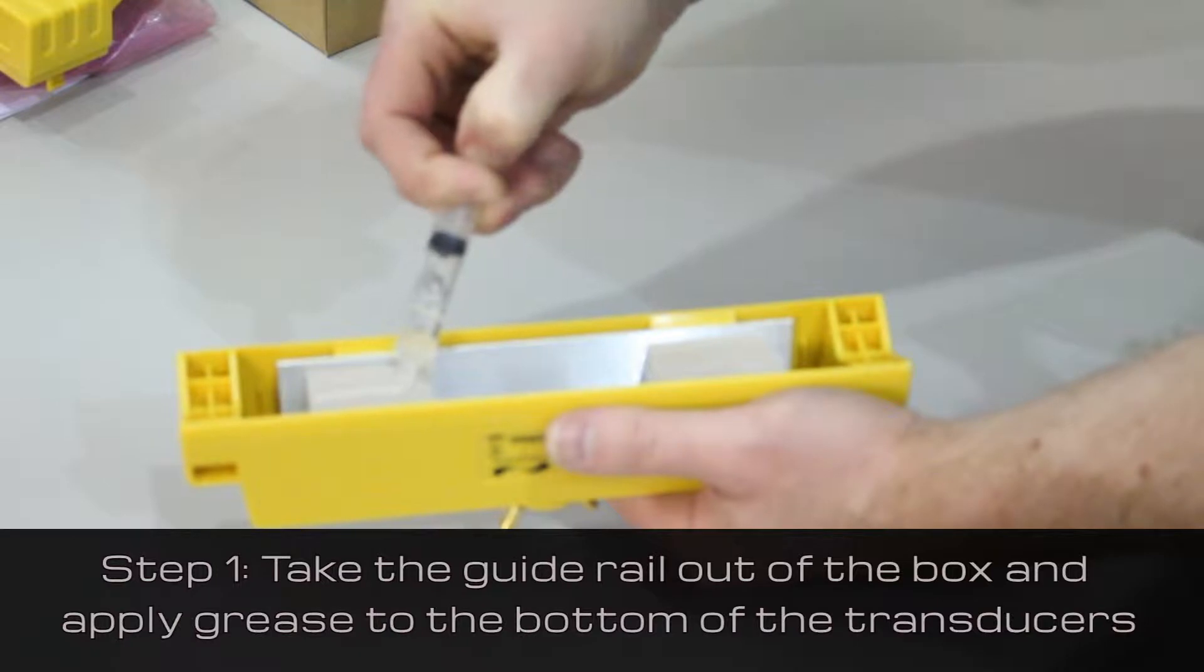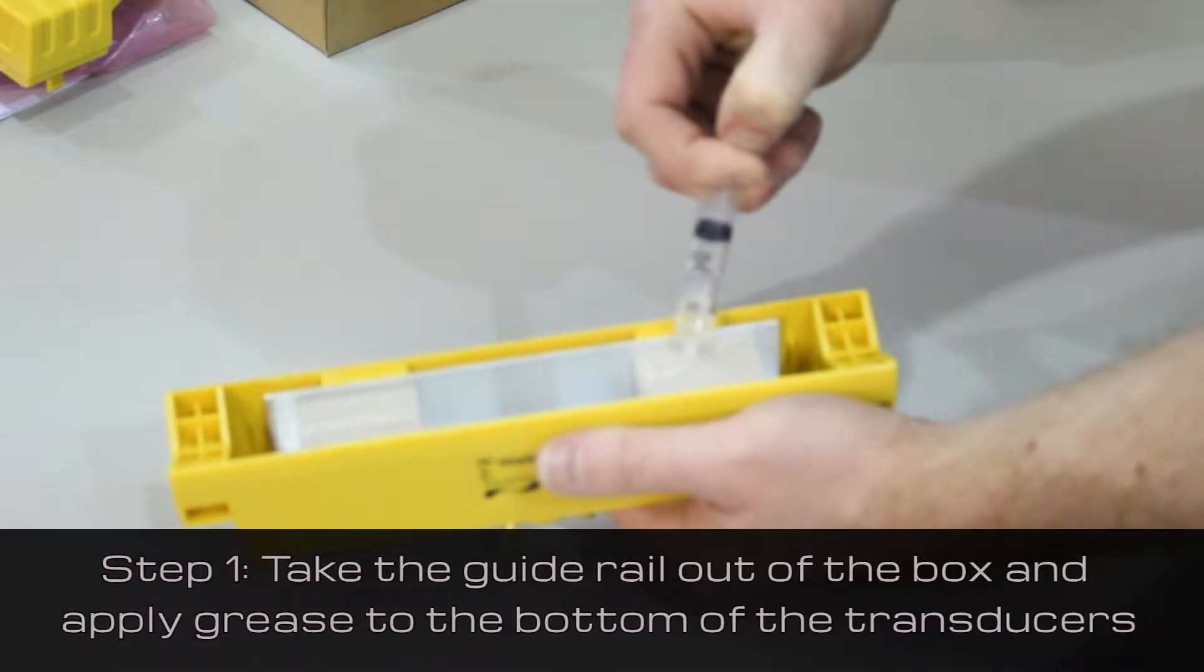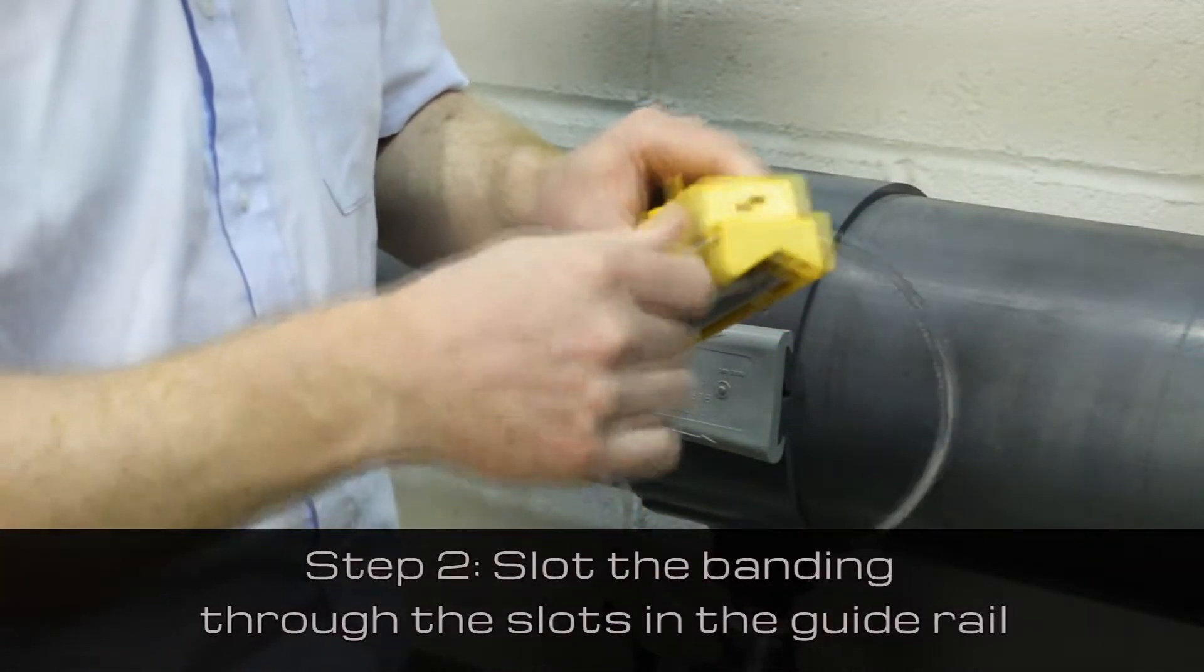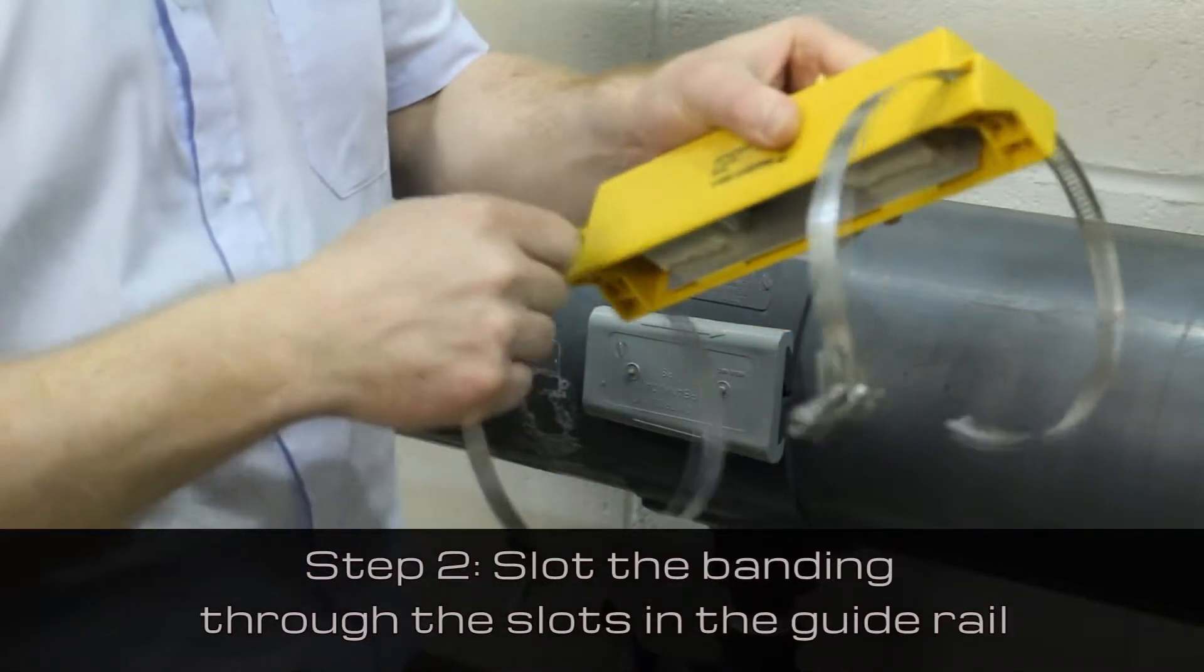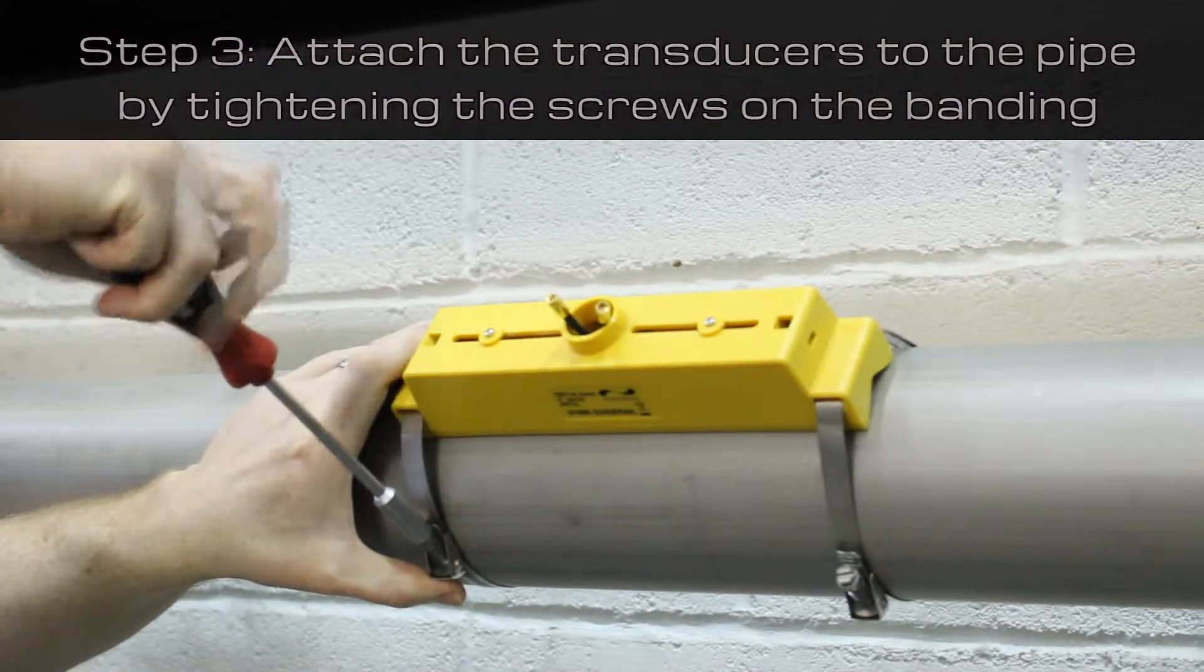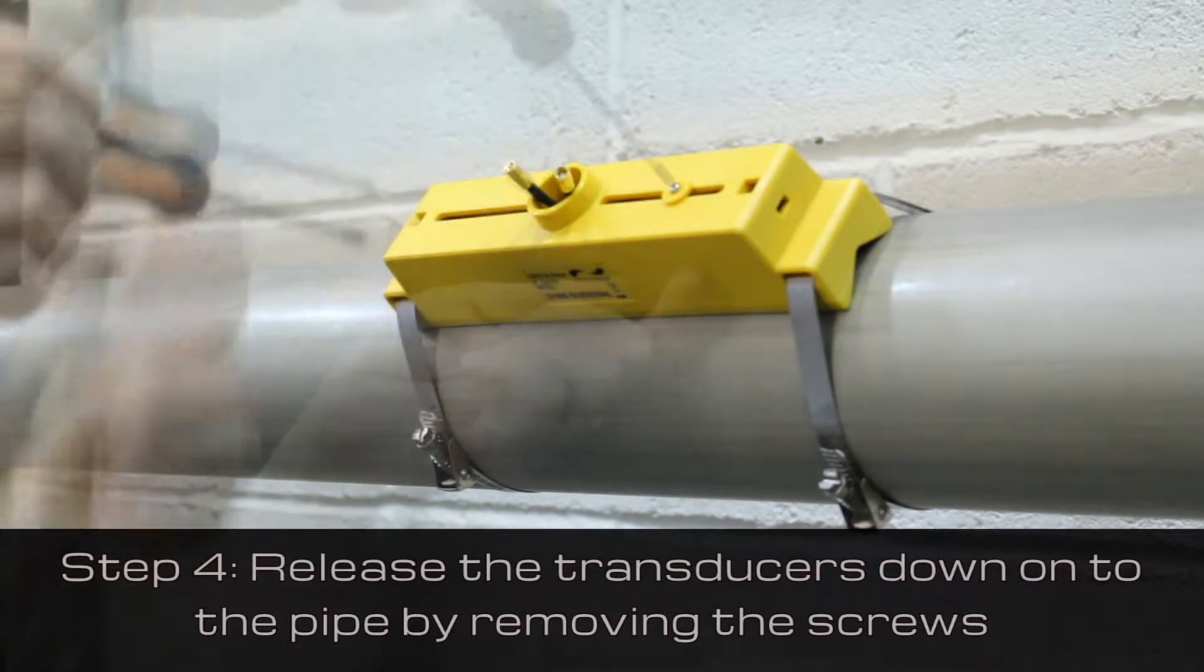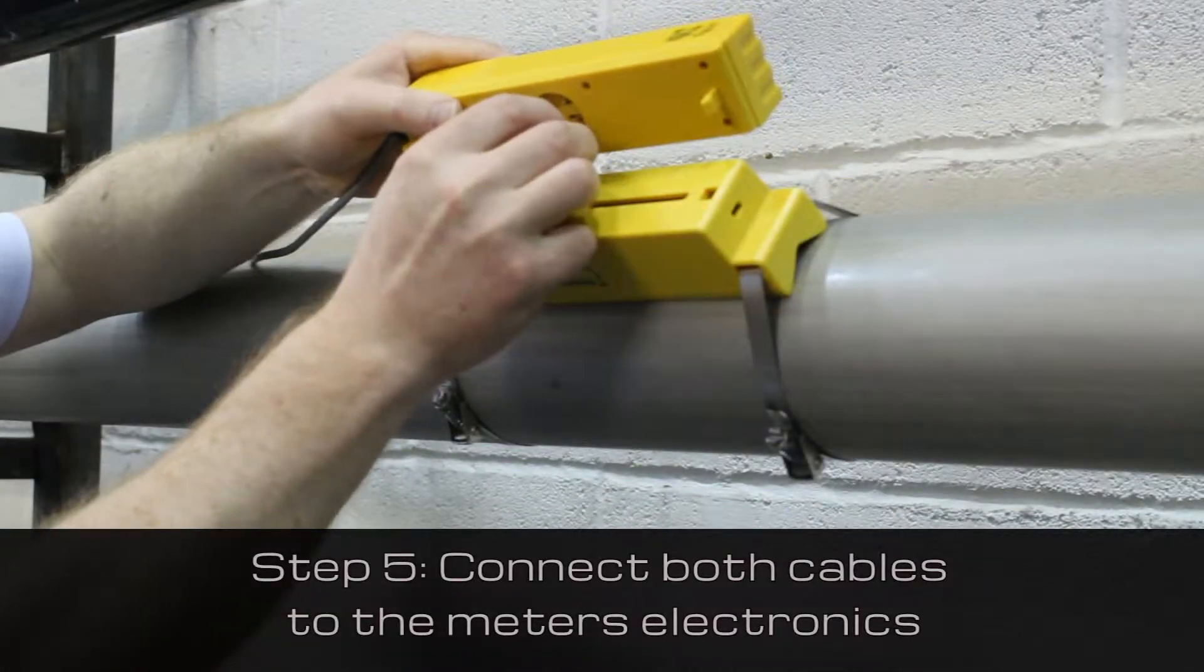First, take the guide rail out of the box and apply grease to the transducers. Then slot the provided banding through the slots in the guide rail. Next, attach the transducers to the pipe by tightening the screws on the banding. Release the transducers down onto the pipe by removing the screws, then connect both cables to the meter's electronics.